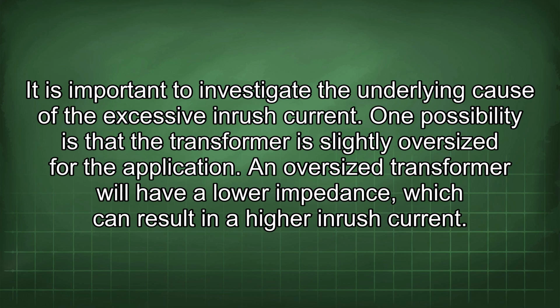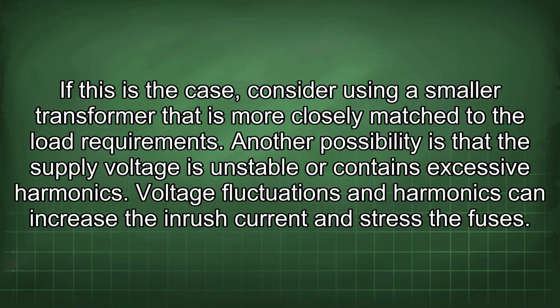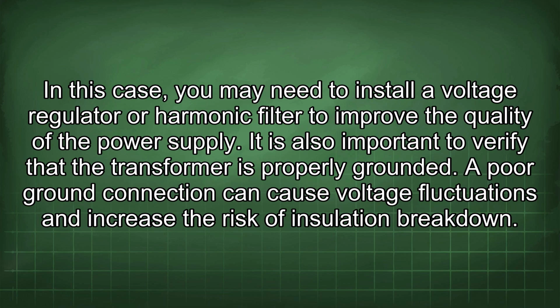One possibility is that the transformer is slightly oversized for the application. An oversized transformer will have a lower impedance, which can result in a higher inrush current. If this is the case, consider using a smaller transformer that is more closely matched to the load requirements. Another possibility is that the supply voltage is unstable or contains excessive harmonics. Voltage fluctuations and harmonics can increase the inrush current and stress the fuses. In this case, you may need to install a voltage regulator or harmonic filter to improve the quality of the power supply. It is also important to verify that the transformer is properly grounded. A poor ground connection can cause voltage fluctuations and increase the risk of insulation breakdown.